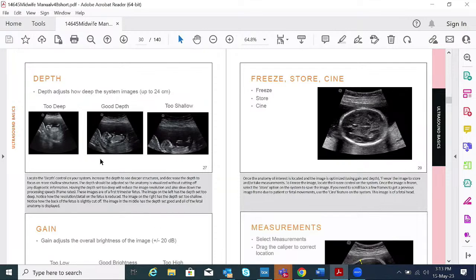Just as you can see here on the three images, too deep, it is down, so you're not really seeing it clearly. You might be tempted to zoom, but again, zoom might reduce your quality and drop your frame rate. So most of the time we would just want to increase the depth. Locate the depth control on your system, increase the depth to see deeper structures, and decrease the depth to focus on more shallow structures. The depth should be adjusted so the anatomy is visualized without cutting off any diagnostic information. Having the depth set too deep will reduce the image resolution and also slow down the processing speed, the frame rate.